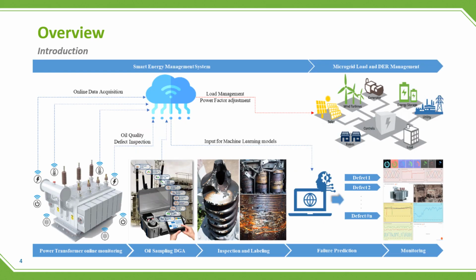So, diagnosing power transformers using machine learning algorithms involves several key steps. The first step is power transformer online monitoring, which is monitoring the key performance indicators to identify any potential issues with the power transformer. These KPIs may include temperature data in different parts of the power transformer, such as the winding, the core, and the oil tank, as well as the levels of different gases resulting from arcing in the oil, water content, and electrical data such as the root mean square of current, voltage, interfacial voltage, power factor, and all necessary data. The second step is oil sampling for dissolved gas analysis, which is an offline operation that helps to identify any issues within the power transformer.